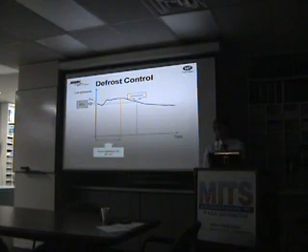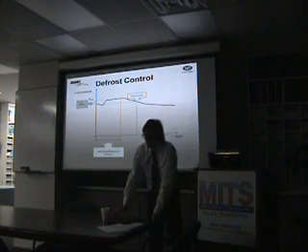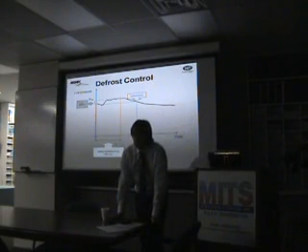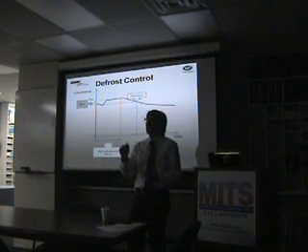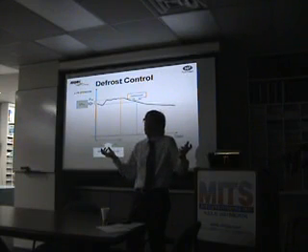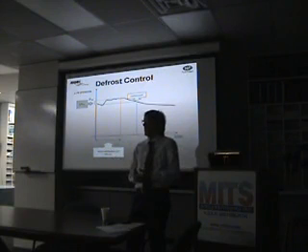It took several years to define this method, but this is the most reliable, and being dynamic, we don't affect the COP. If you would like to be efficient and safe, most of our competitors in Europe fix a time under a certain temperature of the coil and defrost even if they don't need to.